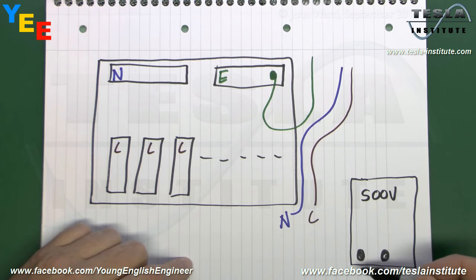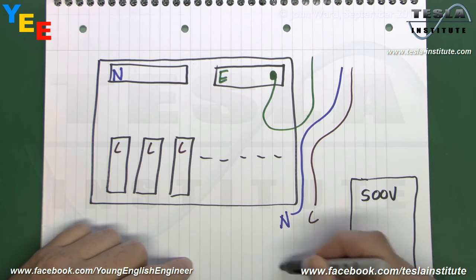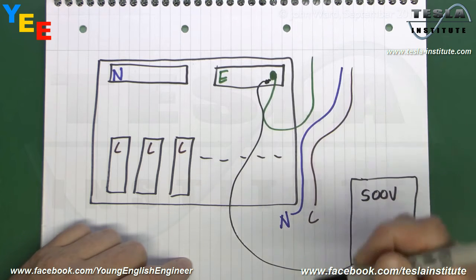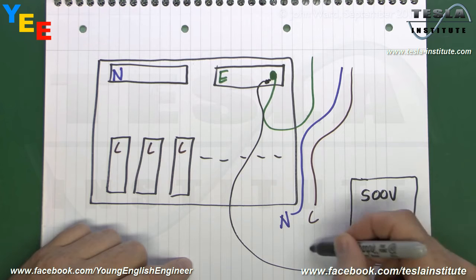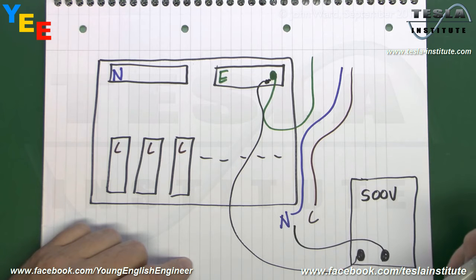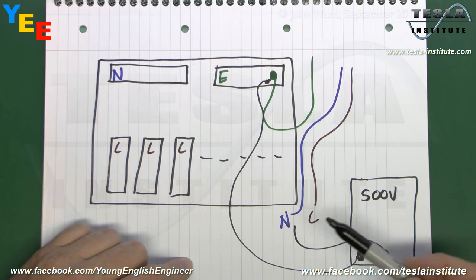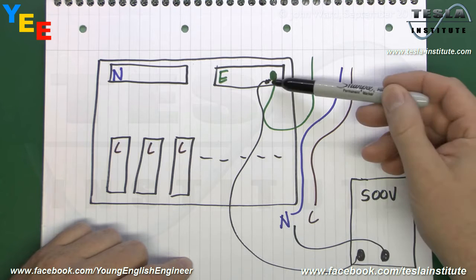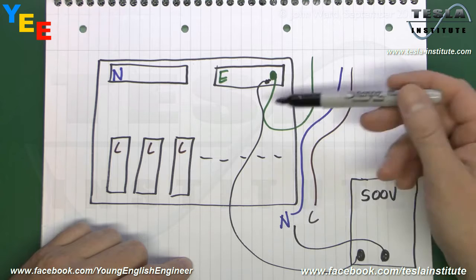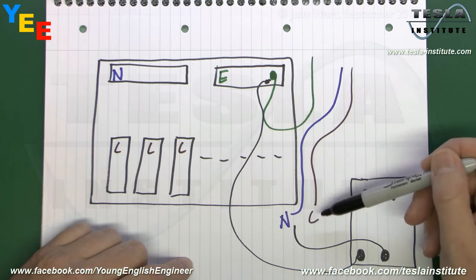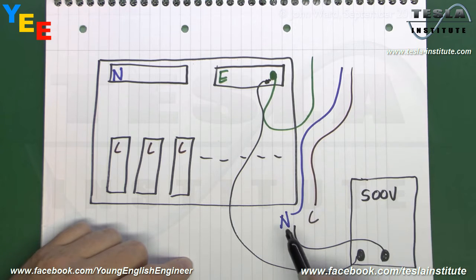And in terms of the test you're going to be doing, it's a question of connecting one lead from here to the earthing of the installation, and then the second one would connect to either the neutral or the live as required. And then you press the button, it will display the actual resistance on the front. Now ideally, in an installation you would test between the earth and neutral, and then test between the earth and the line conductor, and then finally you would actually test between the neutral and the line as well.